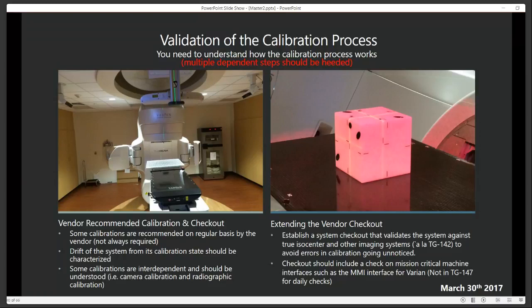And so we extend our checkout, as we talked about, using TG147 in a DICOM plan that actually checks not only precision, but also accuracy relative to IsoCenter and relative to all of our other imaging systems related to the IsoCal on our TrueBeam. That makes sure that when I say I'm going to IsoCenter with my cone beam, it agrees in my SGRT system, it agrees with my kV system, and it agrees with my MV system. It also checks all the dynamic tracking and latencies and obstruction tests that you're supposed to do for TG147 on a daily basis.